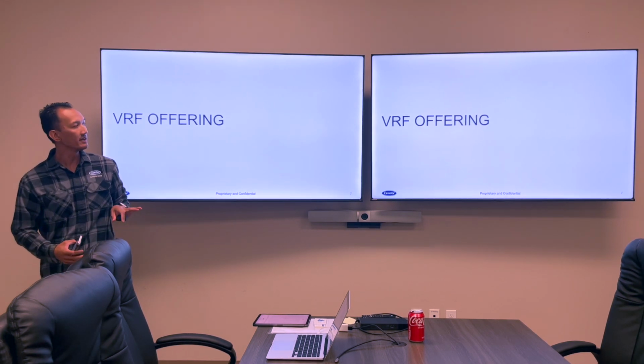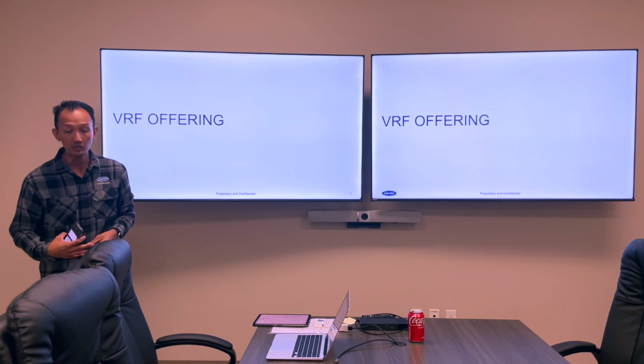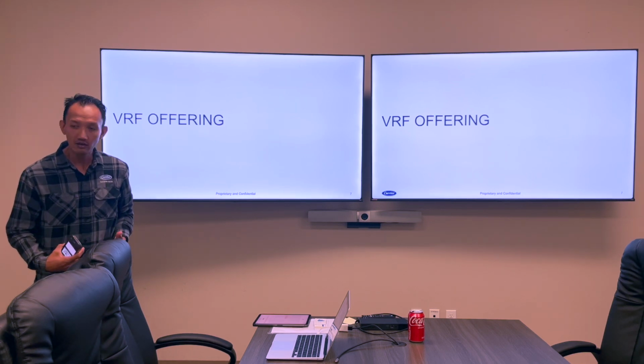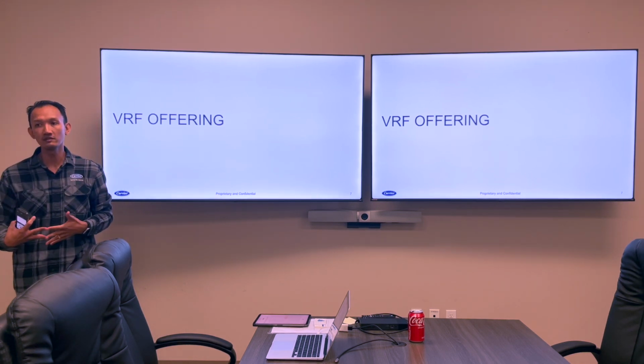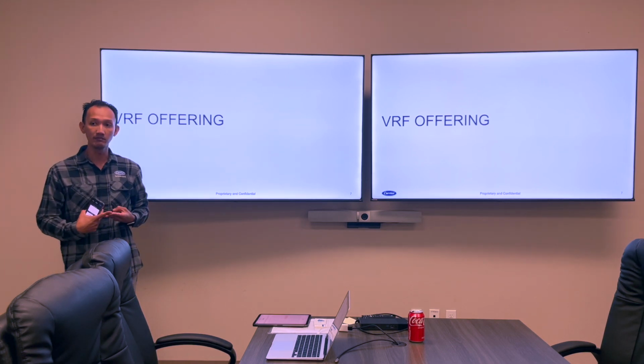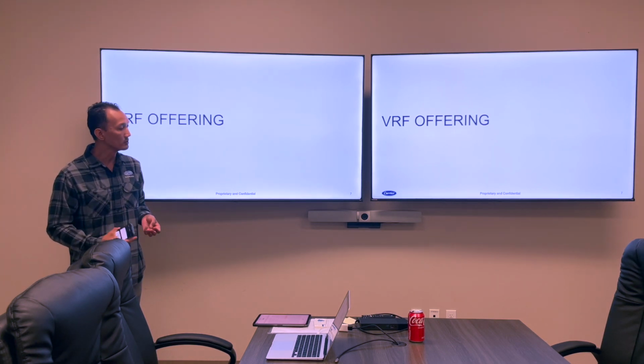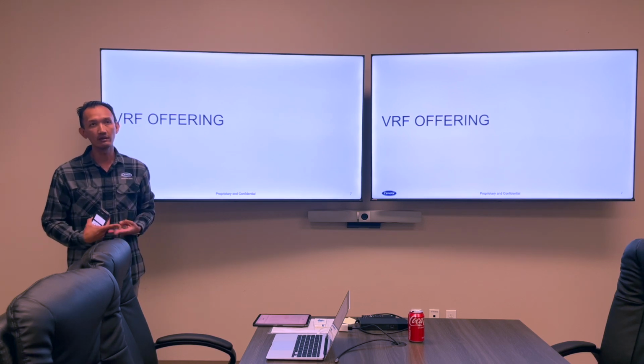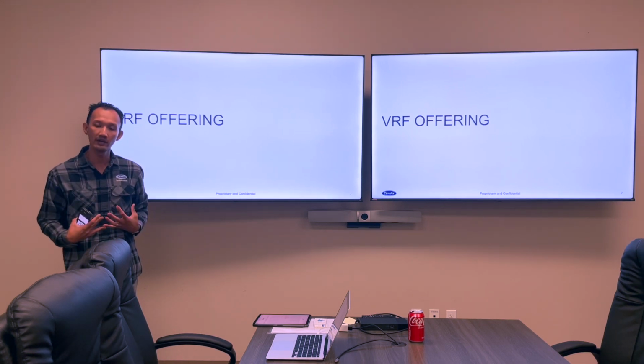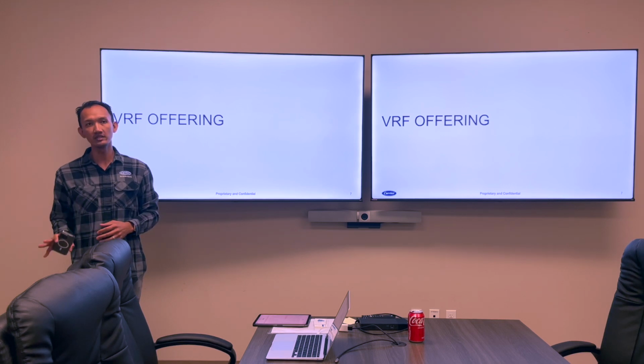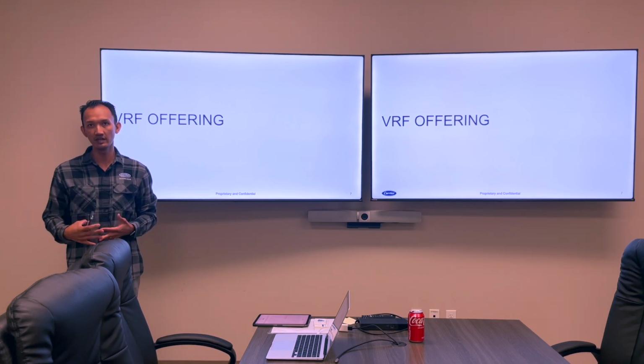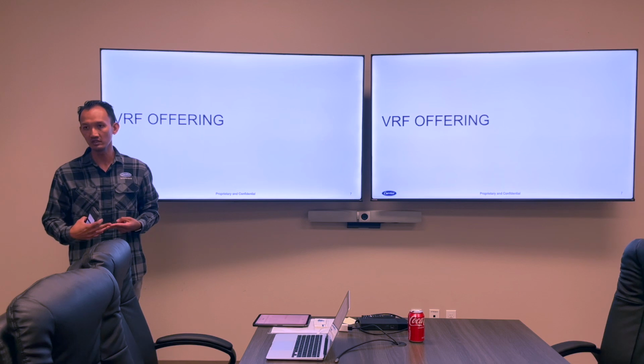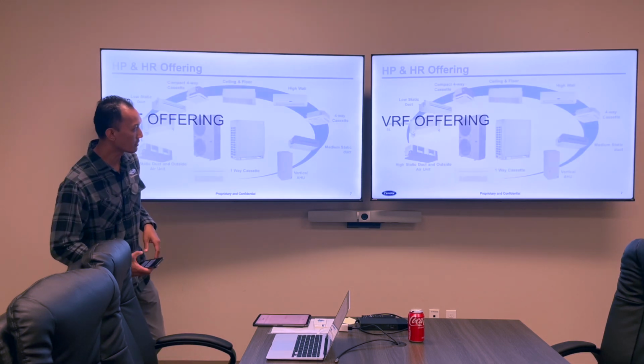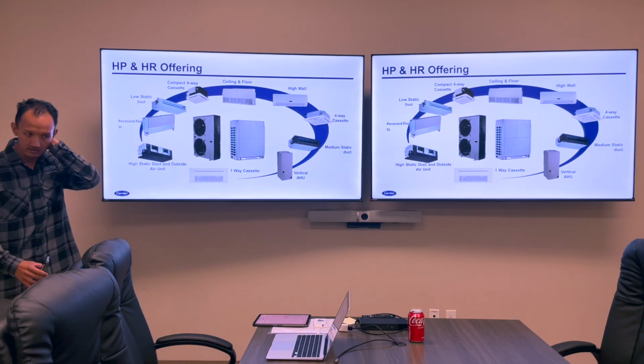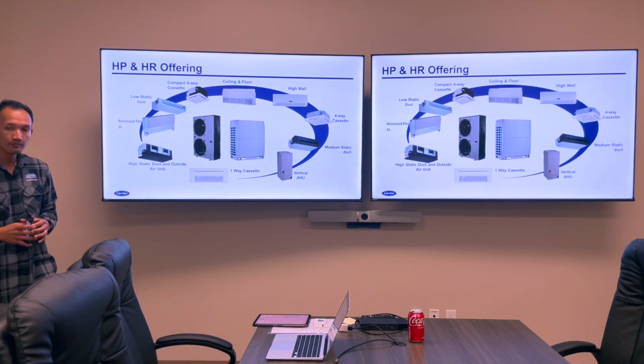Excellent. And Renee kind of alluded to 2-pipe and 3-pipe. So Carrier is unique in that we're the only manufacturer that provides both a 2-pipe and a 3-pipe heat recovery system. Typically you have 2-pipe, that's Mitsubishi and Carrier branded, and then pretty much almost everybody else on the heat recovery side is 3-pipe. So Daikin, LG. We have our Toshiba Carrier line, and then I'll go over briefly our product offerings as far as our 2-pipe and 3-pipe.